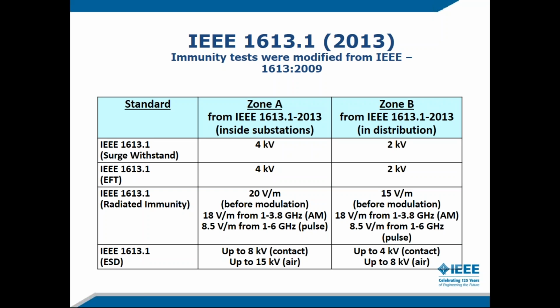So if you look down, I'm not going to go into every test level, but obviously if it's further away, outside the fence, quote unquote, Zone B, there are lower test levels. And you can kind of scan them yourself. The ESD numbers inside are pretty typical of what we would test up to for contact and air discharge. And then in the radiated immunity, because the document that was relied upon only went up to 6 gigahertz, and it was actually spot frequencies, there's an array of some strange numbers from 8.5 to 18 volts per meter. But just keep in mind the 15 and 20 for a moment for the radiated.